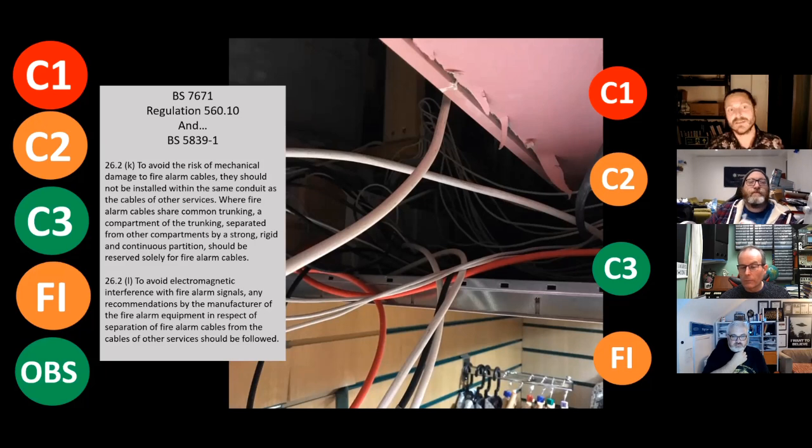Again, if you speak to manufacturers, they've got wiring data information about how you wire these circuits. Now, anybody who's installed a twin flex system, which a lot of electricians have, will know if you run the fire alarm cables next to LV cables, quite often you do get interference and they don't function how they're supposed to. So we're not following manufacturers' instructions either. No.